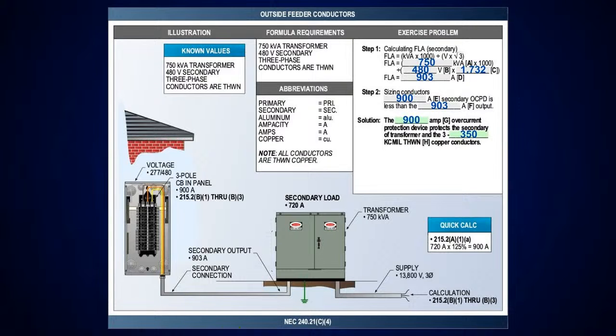Now, remember in this case, and we covered this earlier, 240.4(B) deals with overcurrent devices 800 amps or less. Once I get over 800 amps, then I'm looking at 240.21(C). In this case, my conductors have to be equal to or more than the overcurrent protection device at this point, or the load. Okay, so that means I have to be equal to it or drop down. Well, I had a 903 output. I can't exceed it, so I have to drop down to the next standard size, which is 900 amp. And then I'm going to look at what type of conductors I need here. And in this case, I'm going to need 350 kcmil conductors, which I'm going to parallel 3 times, which is going to give you 920 amps. Okay, I just know that off the top of my head because I've done it so many times.